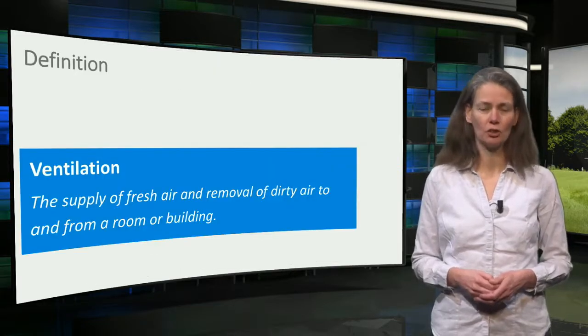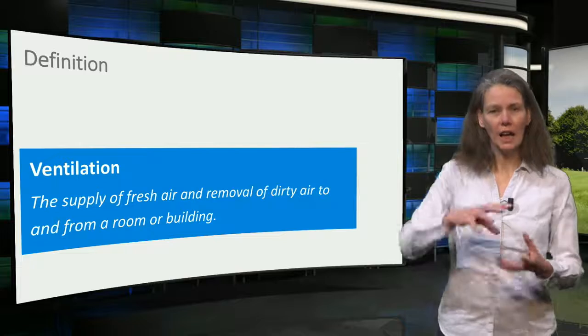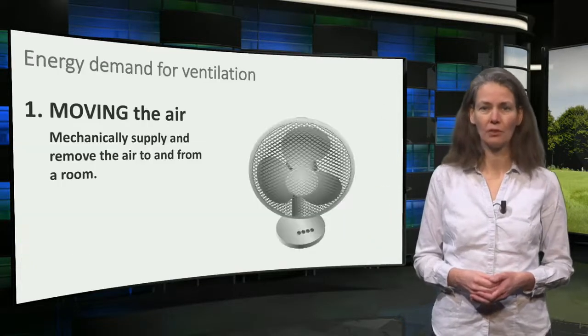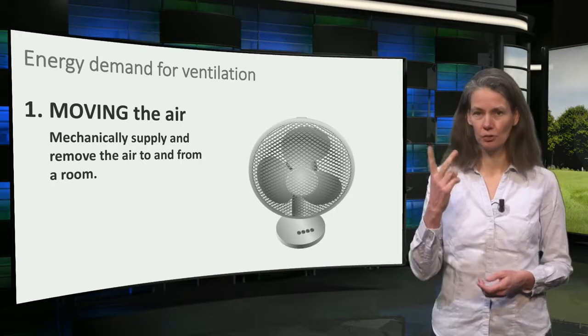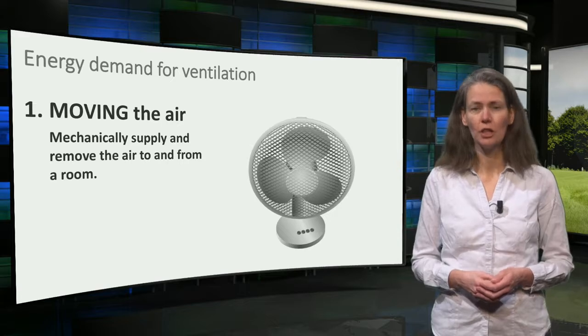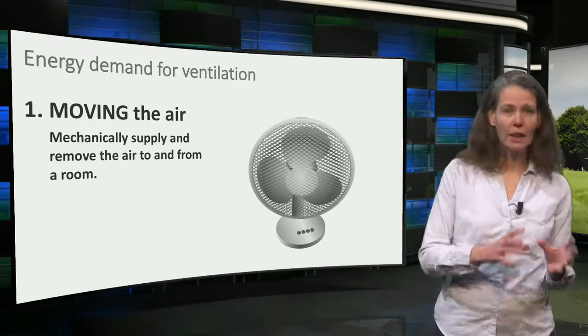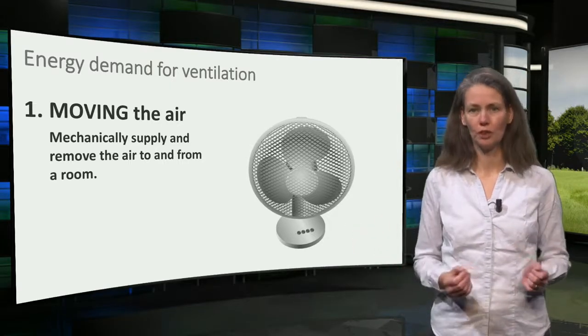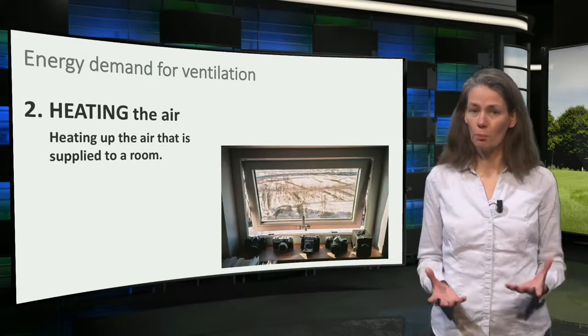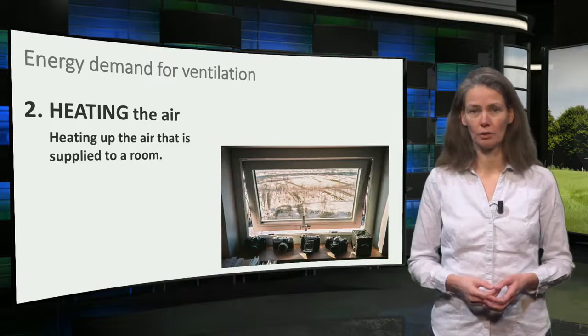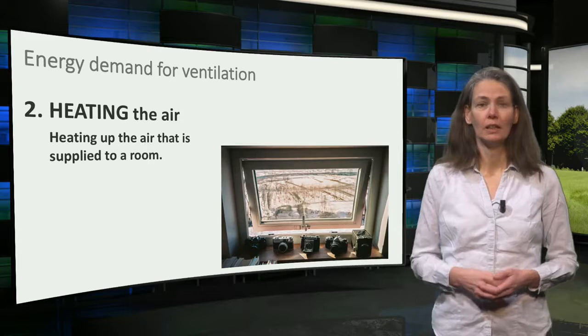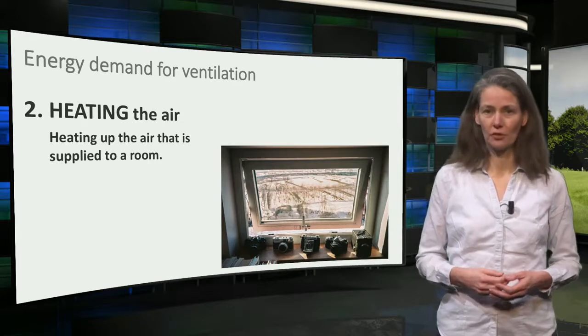Ventilation is by definition the supply of fresh air and the removal of dirty air to and from a room or building. The energy demand for ventilation consists of two aspects. The first aspect is the electrical energy necessary to mechanically supply and remove the air using a fan. Secondly, energy is necessary to heat up the fresh air to the required indoor temperature. The lower the outdoor temperature, the higher the energy demand to heat up the fresh ventilation air.